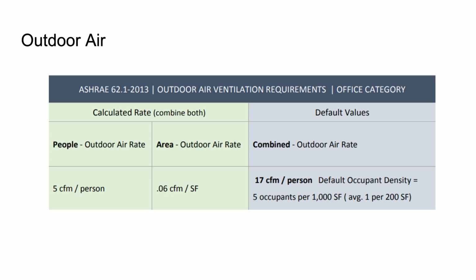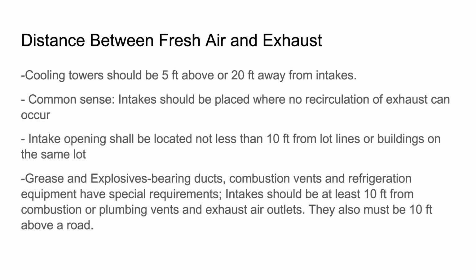Nothing super interesting there, it's what we've already gone over. Distance between fresh air and exhaust. If you want to go ahead, Dan, on this, we sort of covered this, touched on this a little earlier. Cooling towers: 5 feet above or 20 feet away from intakes. That's not something we see a lot, but if you do have a cooling tower, you're introducing humidity into the air. That's basically what it's doing. And so you're going to have the possibility of pulling that in. You don't want to be pulling 100% humid air right back into your return.